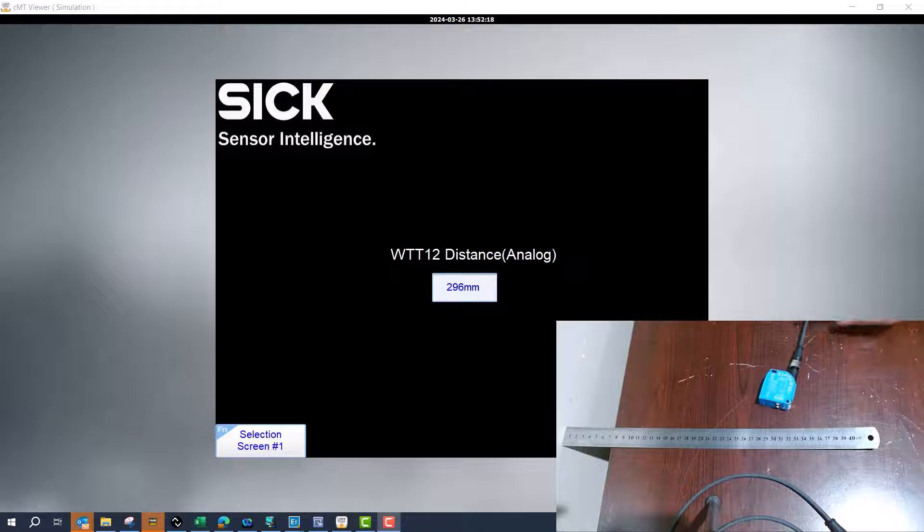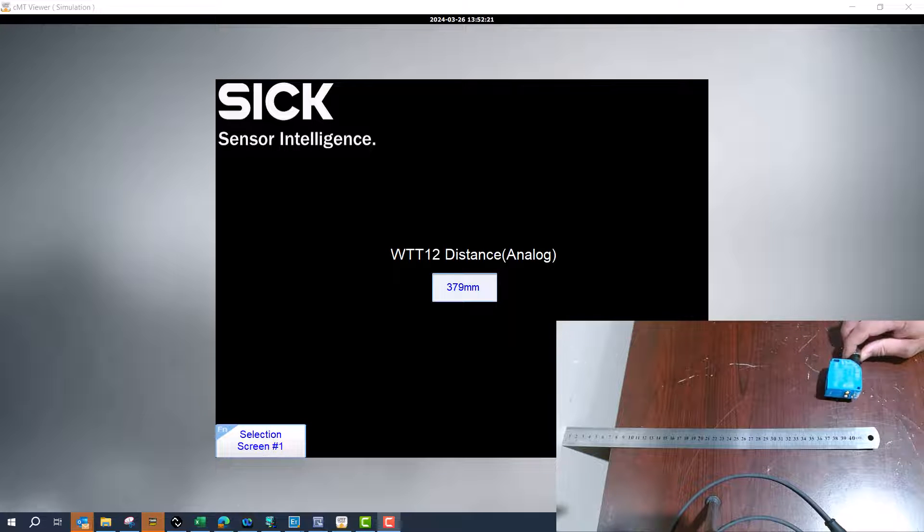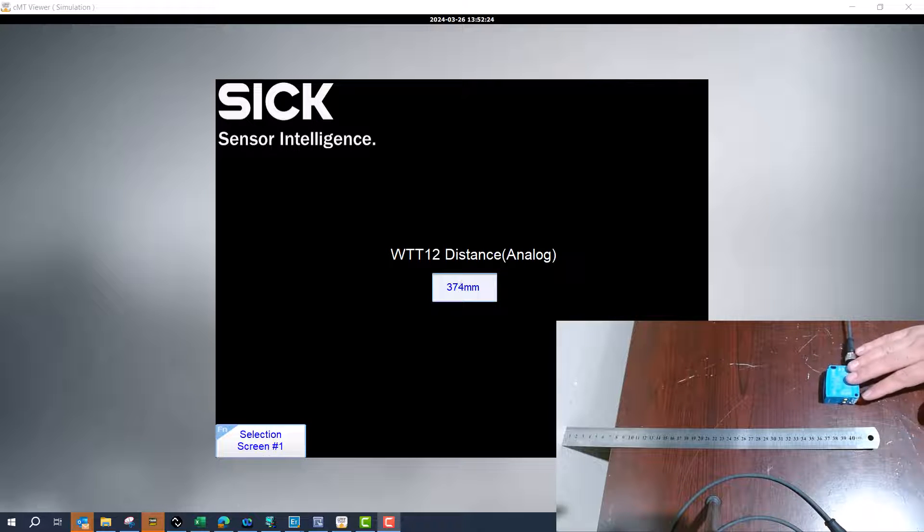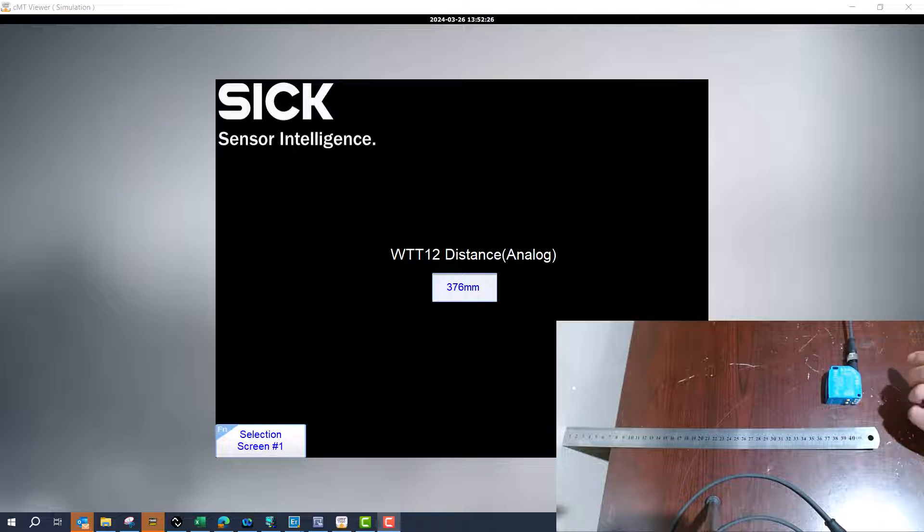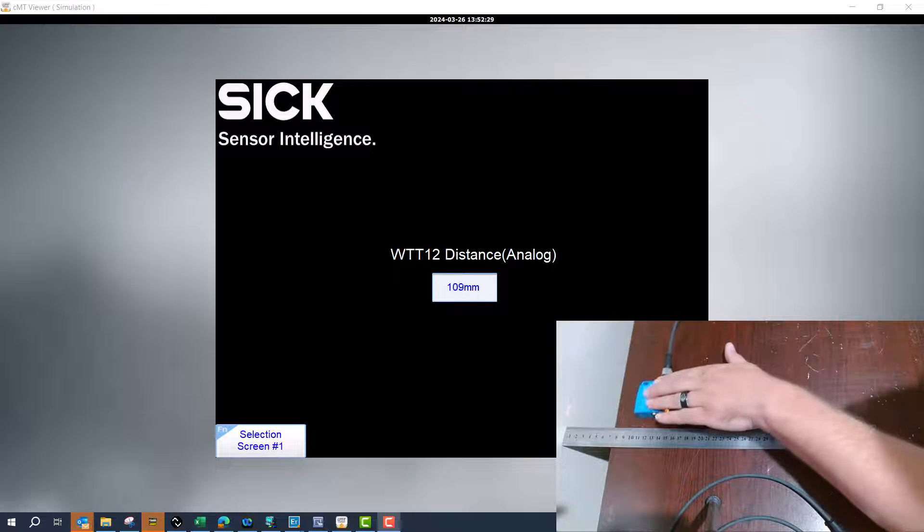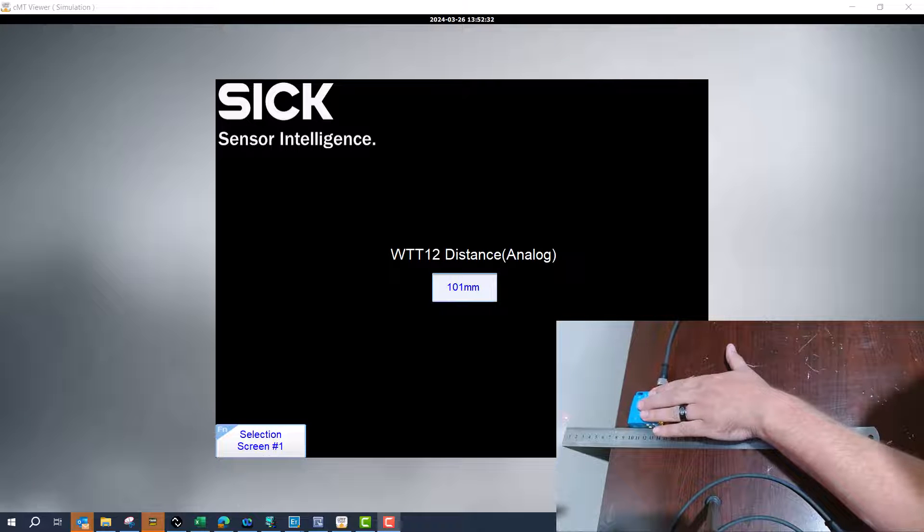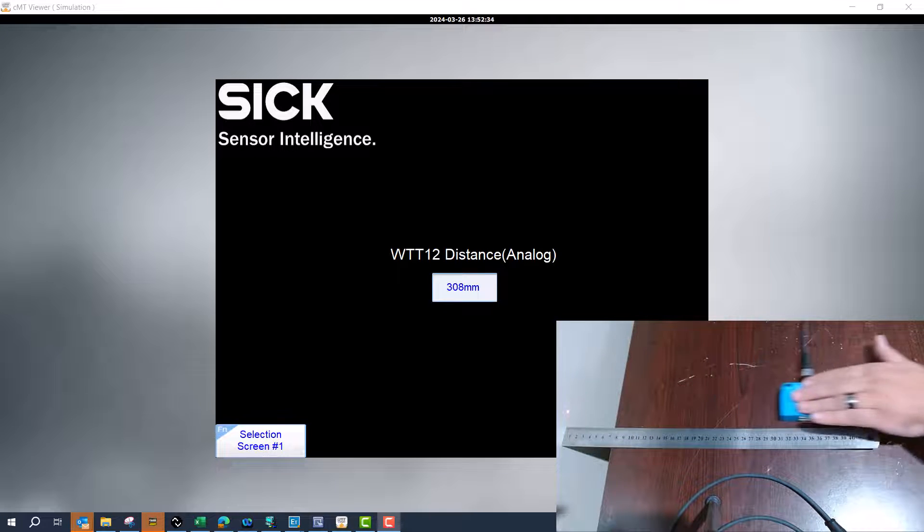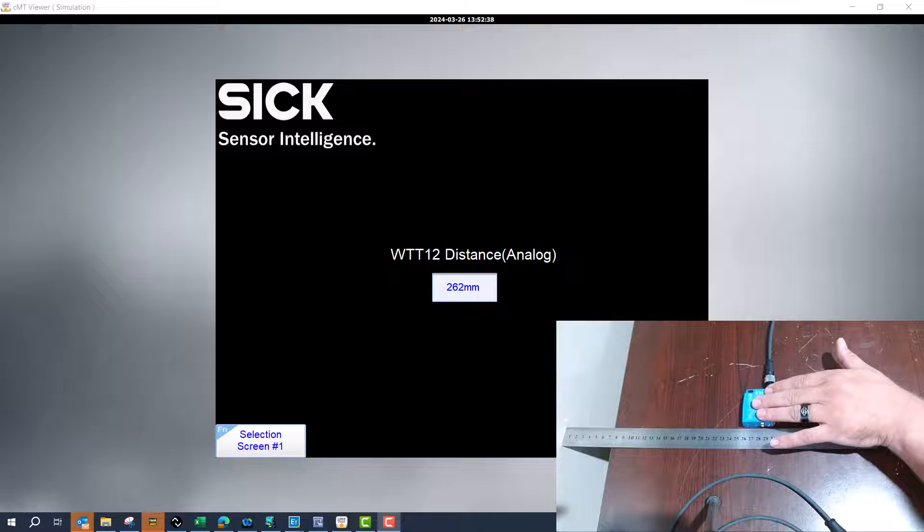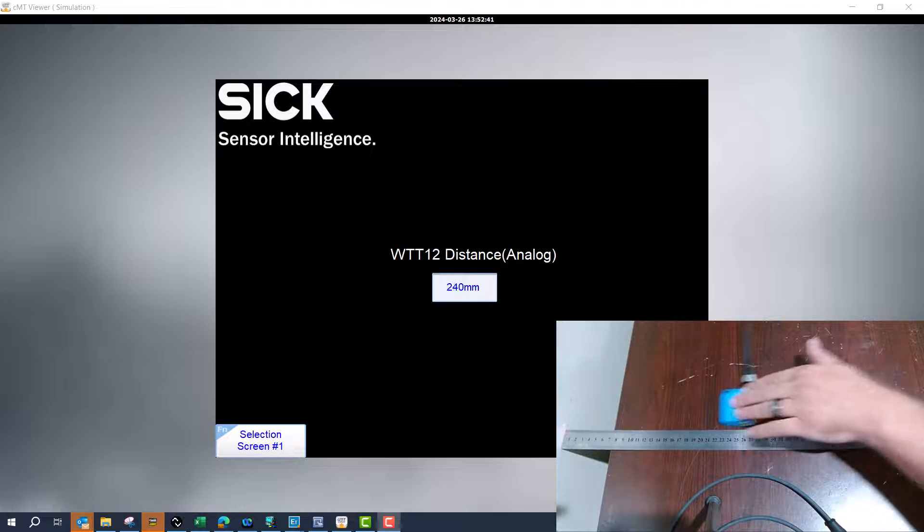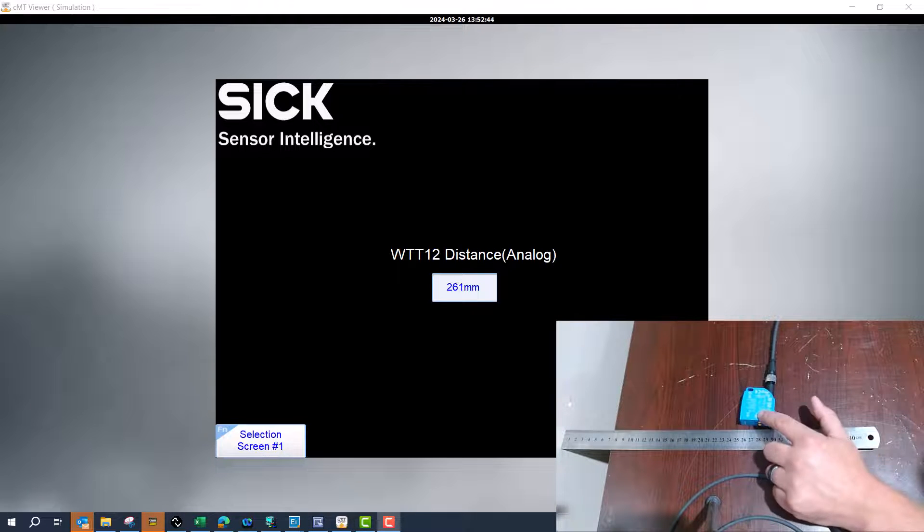But if you want to make custom measurements, like this one I've already set from 100 millimeters to 400 millimeters - so if I put it up to around 100 millimeters and then I come back to around 400 and then 260, so pretty accurate. So what we're going to do is change it on the sensor and then we'll have to change the scaling in the PLC.